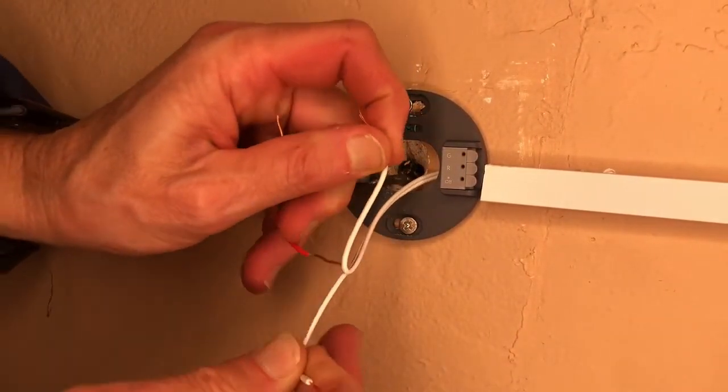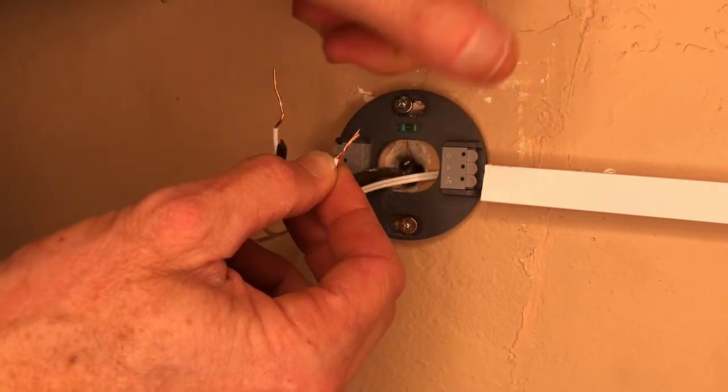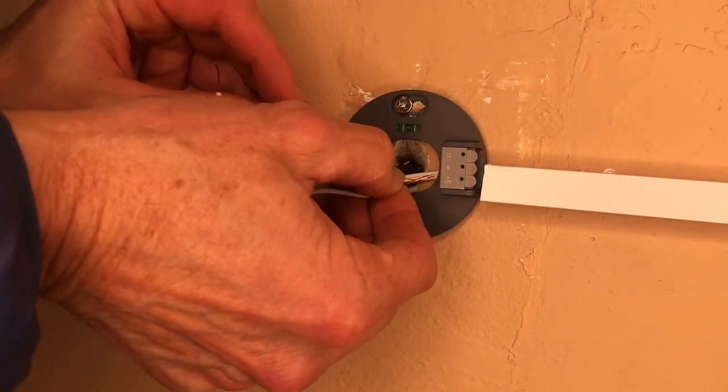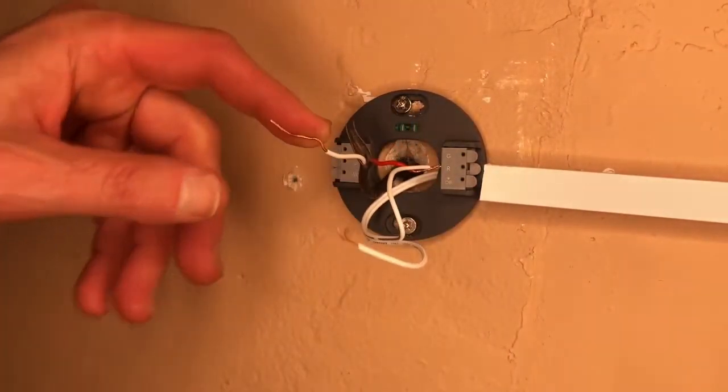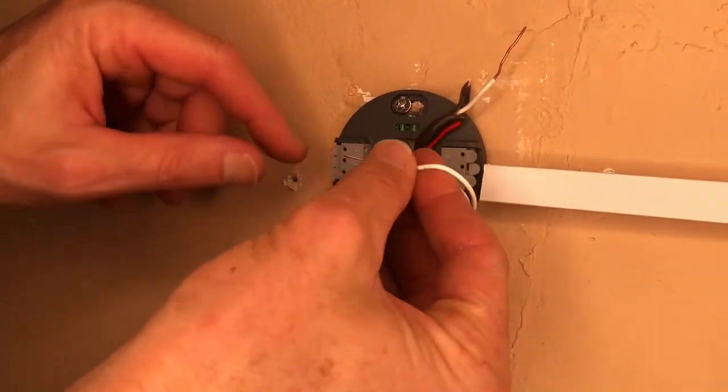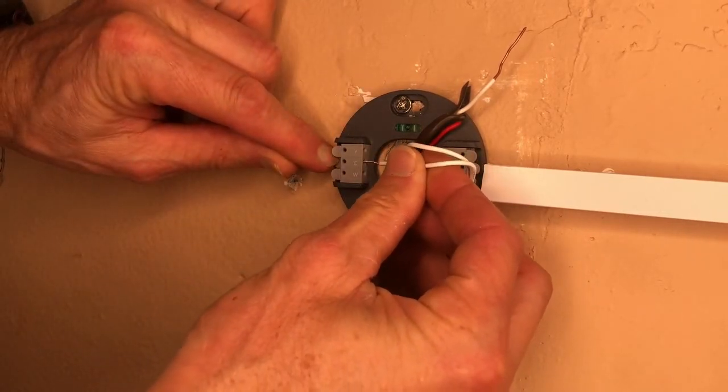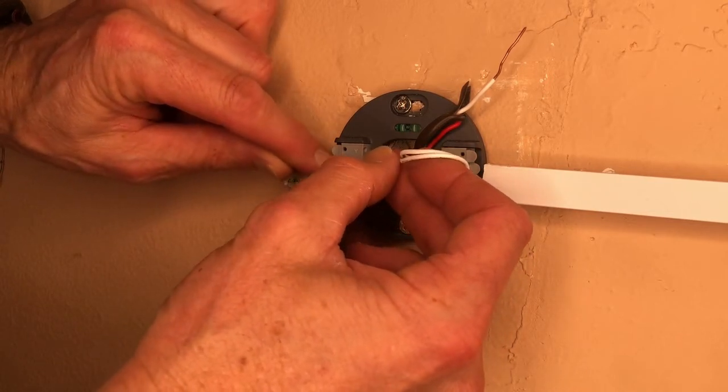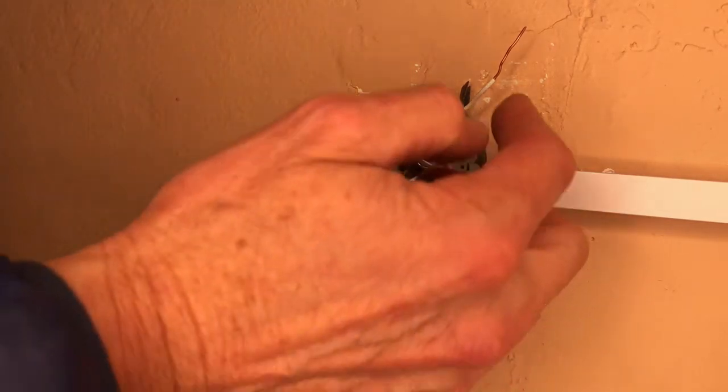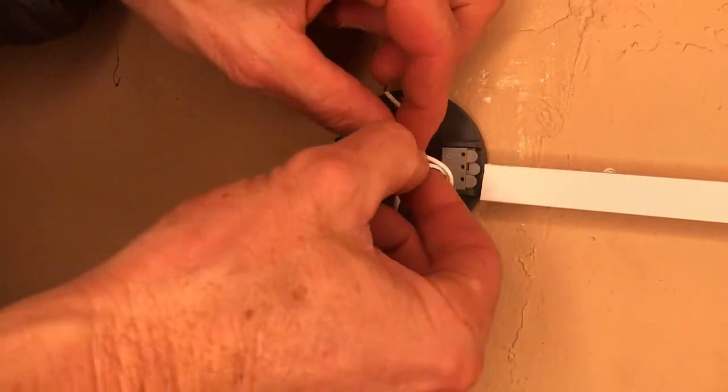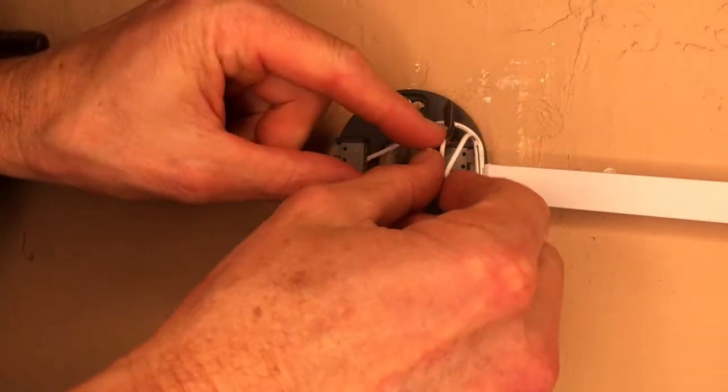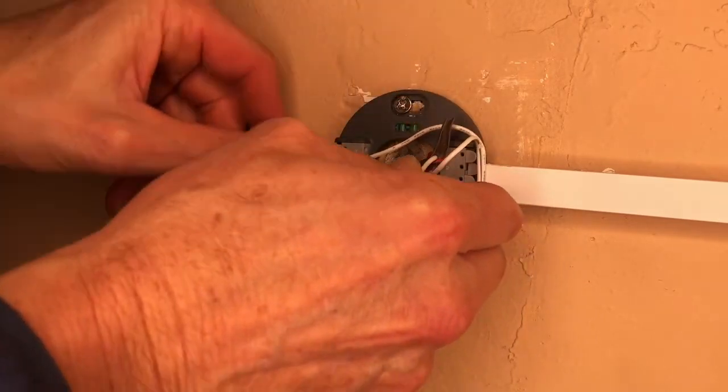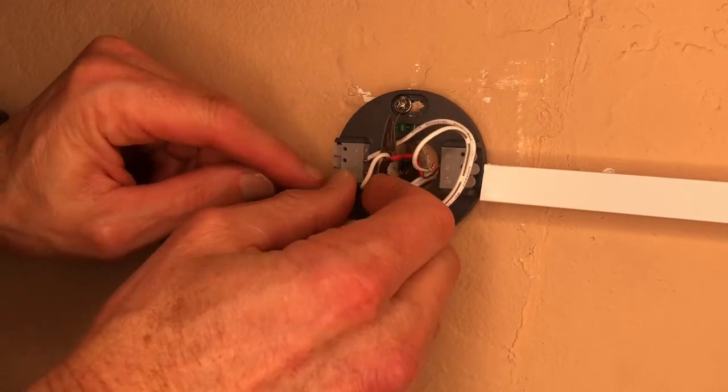Now I'm going to actually hook up the wires. So let's start with one of the C wires going to the 24 volt adapters and the red wire that goes to the heater. You just twist those really tightly together and press them right there into the R slot. Okay, there we go. So next up, we're going to take the other 24 volt adapter wire, press that into the C slot. You see, I just press that little tab down and it opens it up and then I press it in.